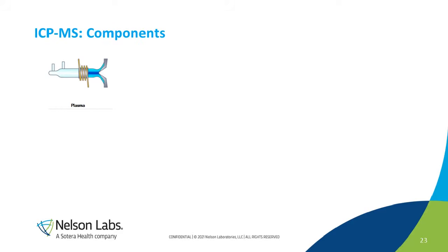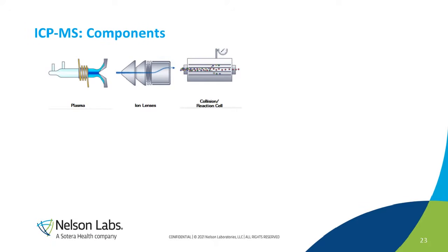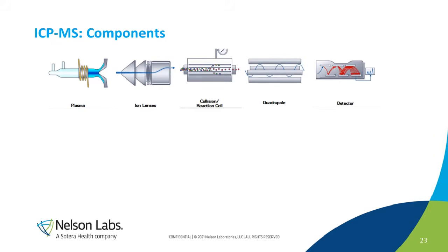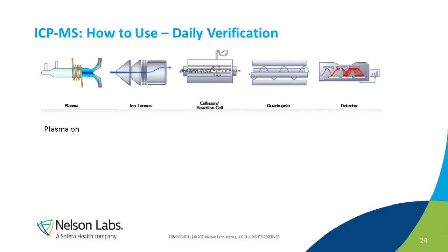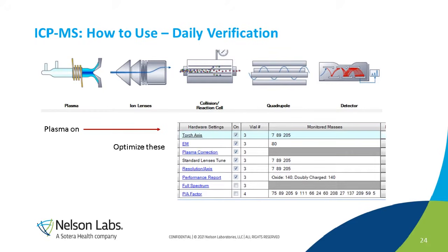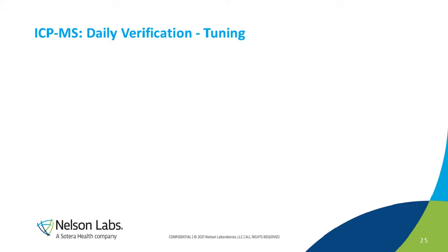Now I need to show a little bit about the component parts of the ICP-MS. There should be the plasma generation part, and then ion lenses, and then the collision and reaction cells, a quadrupole, and detector. So now, when it's going to be actual use, we need to do this kind of step. We need to turn on the plasma. So actually, we already talked about this plasma torch. Then we need to optimize all these parameters for this experiment. Obviously, since I talked about this daily verification, we need to do this every single time if we want to use it.